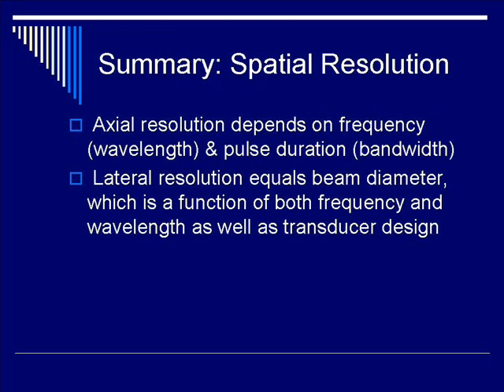In summary, axial spatial resolution depends on the frequency or wavelength and the pulse duration or bandwidth, whereas lateral resolution equals the beam width, which is a function of frequency, wavelength, and transducer design. Let's do another question.